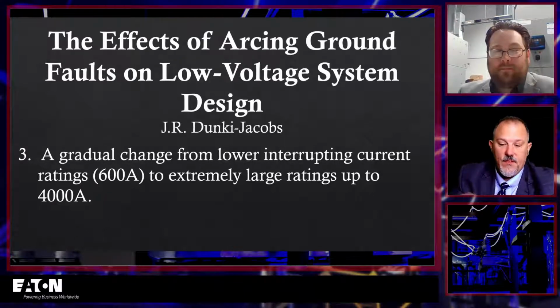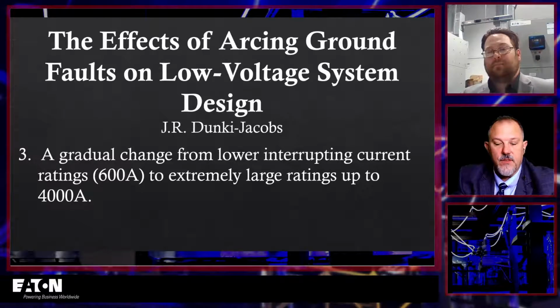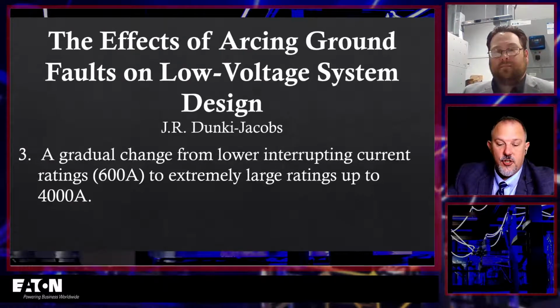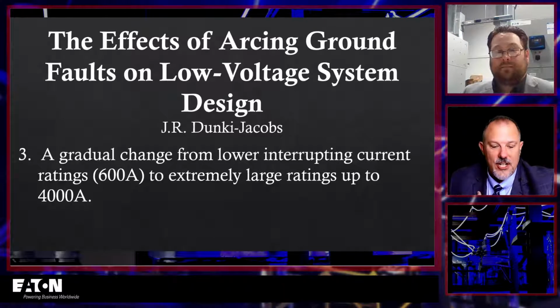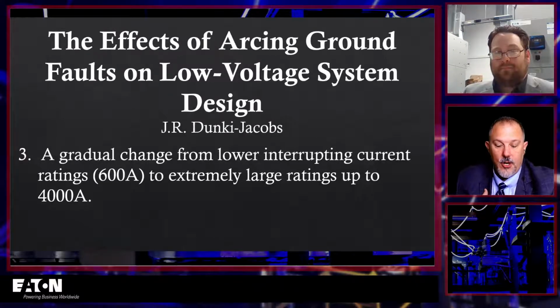That's why 1584 is only looking at three phase fault currents. And it says the delay greatly increases the risk of injury to personnel. So they're talking about arc flash hurting the people who were getting hurt in these areas. During the past several years, at least 5 major cities have reported major electrical equipment damage, and in 2 instances, fatalities have occurred in which low fault currents have persisted for a sufficient time to cause very extensive damage.